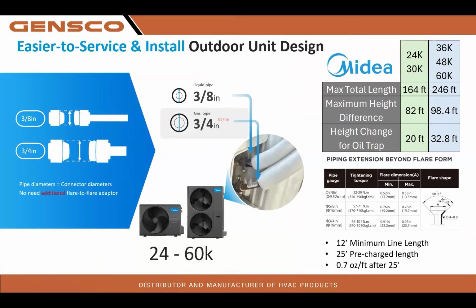Once again, we are using one line set size, 3/8, 3/4 on the 24 to 60K models that Gensco does sell. Our minimum line set length is 12 feet. It is pre-charged to 25 feet in length. That's fantastic. And for those shorter line set lengths, maybe 12, 15, 17 feet, we do not need to take any of the refrigerant out. Just let it run, fire it up. Our total line set length is 164 feet. Total height difference is 82, and height change for an oil trap is 20 feet.